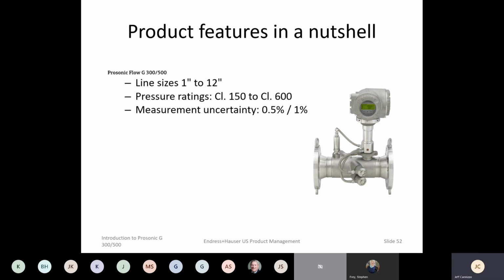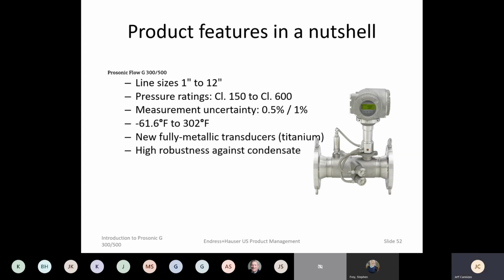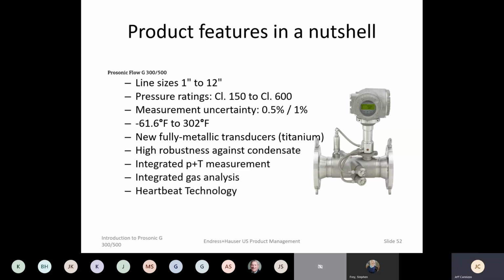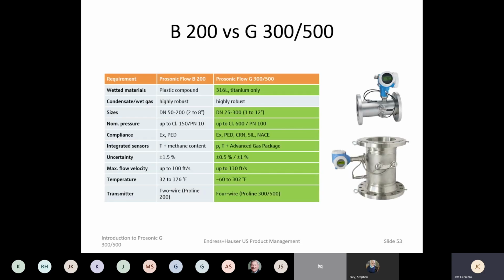But basically, the new meter line size is 1 to 12 inch, pressure ratings up to class 600, extreme accuracy of 0.5%, and higher temperatures up to 302 degrees. It has titanium sensors. The body itself is stainless steel, so we do have some limitations on corrosive gases like chlorines, but it's very robust against condensate, and it does have integrated pressure and temperature measurement. So we can do compensation, and of course it offers heartbeat technology. So, some different meters now for gas flow applications.